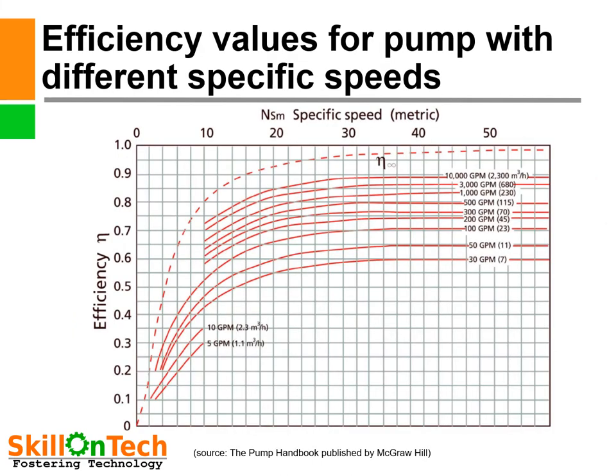A graph of efficiency of pumps with respect to specific speed is shown. This picture clearly shows that high efficiency can be achieved in all three kinds of impellers. Above approximately 20 Ns in metric specific speed, the curve becomes flatter, indicating that the best efficiency point can be achieved across all three impeller types.